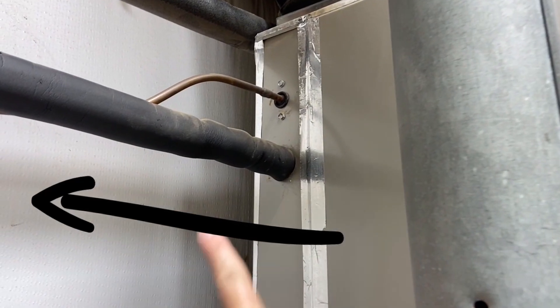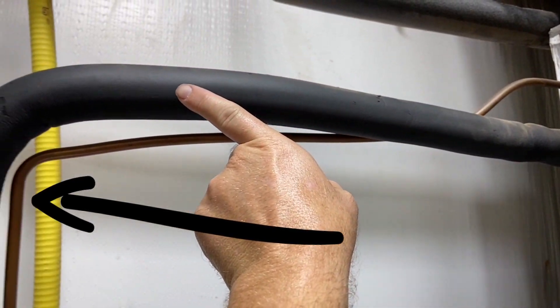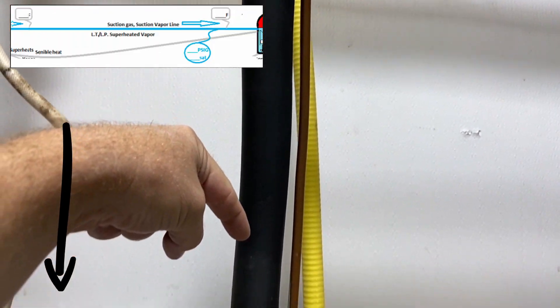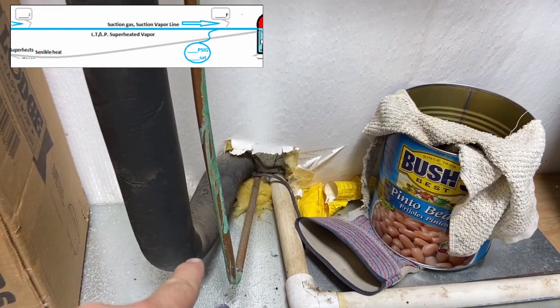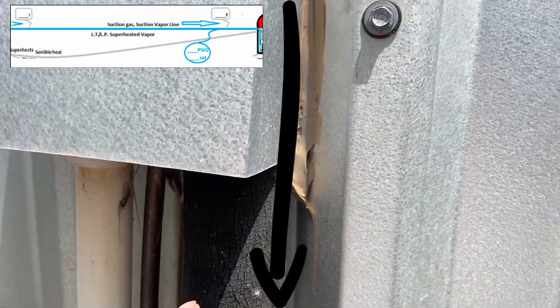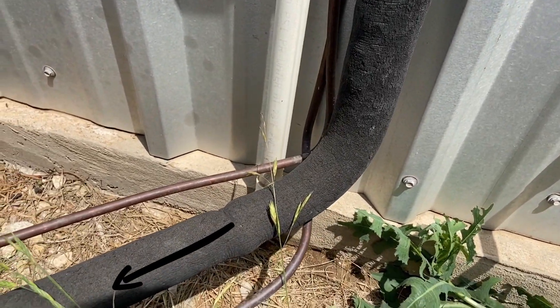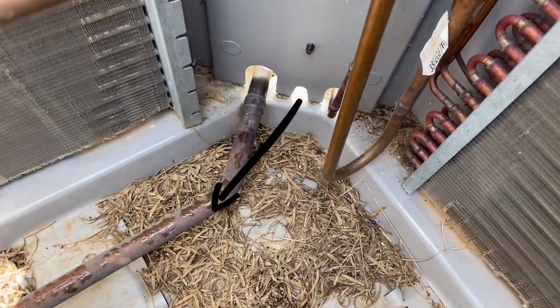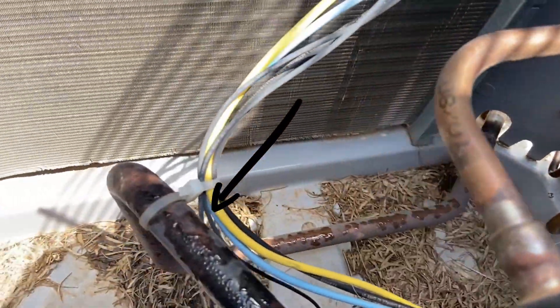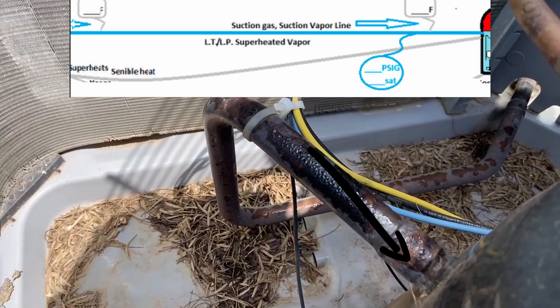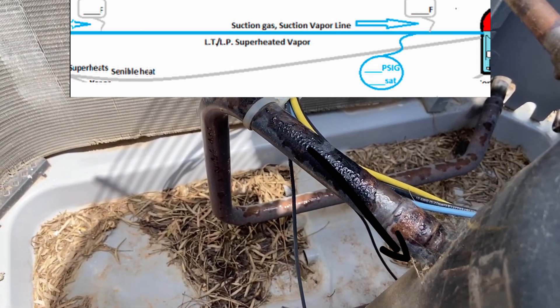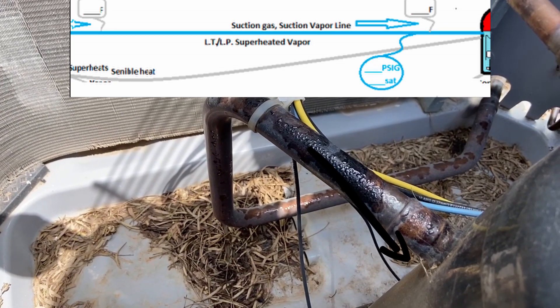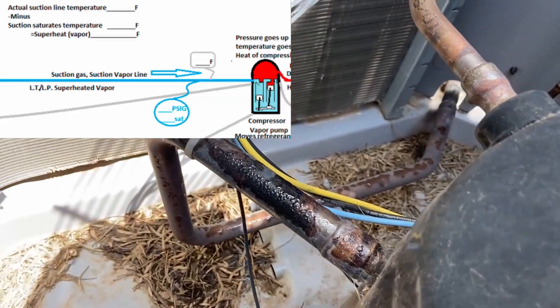Here we have our suction line, also called our gas line — it's a low temperature, low pressure superheated vapor. This line is insulated because we do not want to absorb any more heat. We follow the suction line all the way outside, continuing back towards the outdoor unit. The suction line goes through a valve and we can see the fat line coming in along the bottom, going right back to the compressor. We want to make sure our superheat is above five degrees to protect the compressor from any liquid refrigerant.